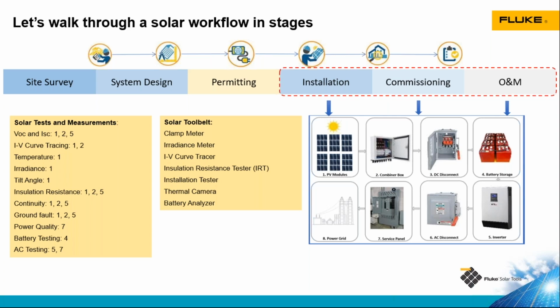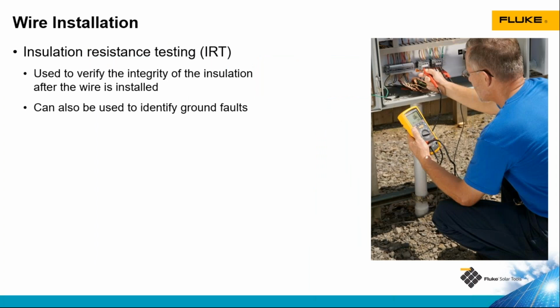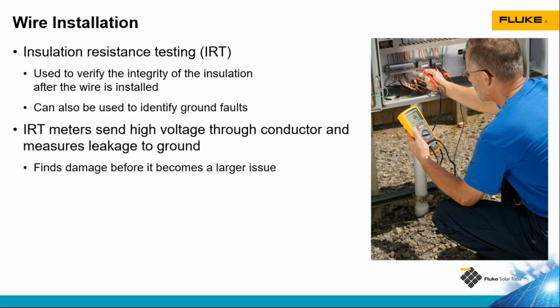In the life cycle of a solar installation, there are many different stages. The stages we're going to focus on in this presentation are installation, commissioning, and operations and maintenance, or O&M, because those are the stages in the life cycle of solar that most of our testing is done. During installation, a really good test to do is insulation resistance testing. We can use this to find out if there has been any damage caused to the conductors. We can also use it to look for ground faults, both during the installation, commissioning, and operations and maintenance phases. What insulation resistance testing is doing is sending a high voltage, low current signal through the wire and looking for current flowing to the ground. At installation and commissioning, we can use it to find issues before they become bigger problems and cause additional damage.